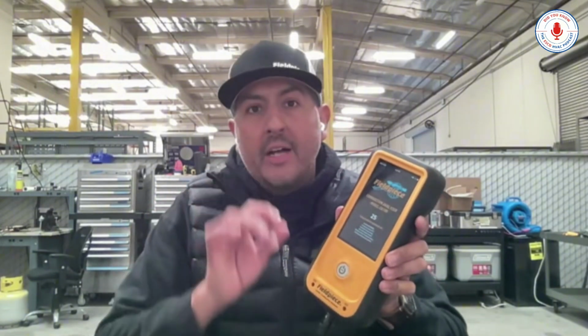Step number two is you want to power on your combustion analyzer and let it go through its warm-up process. So I'm going to start this right here - there's another click that unlocks the sensors so they're able to start reading, sensing the oxygen and taking readings. The combustion analyzer goes through a warm-up process checking the different sensors, checking that everything's plugged in properly and tuned up and ready to go. It's also making a reference for your oxygen sensor to 20.9%.